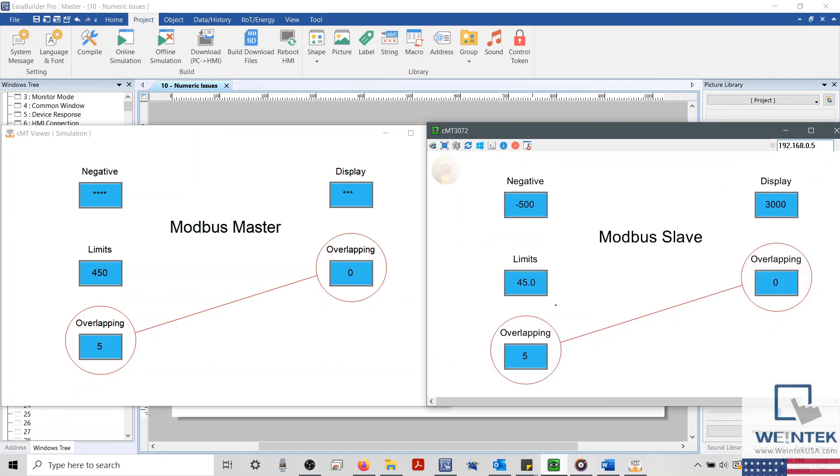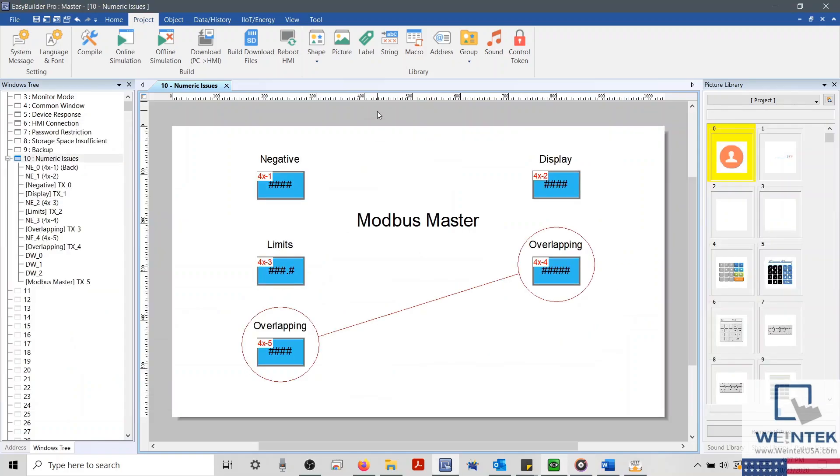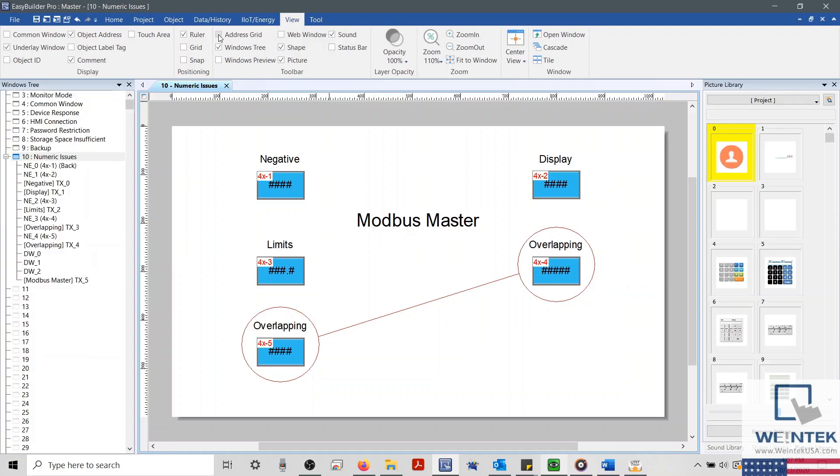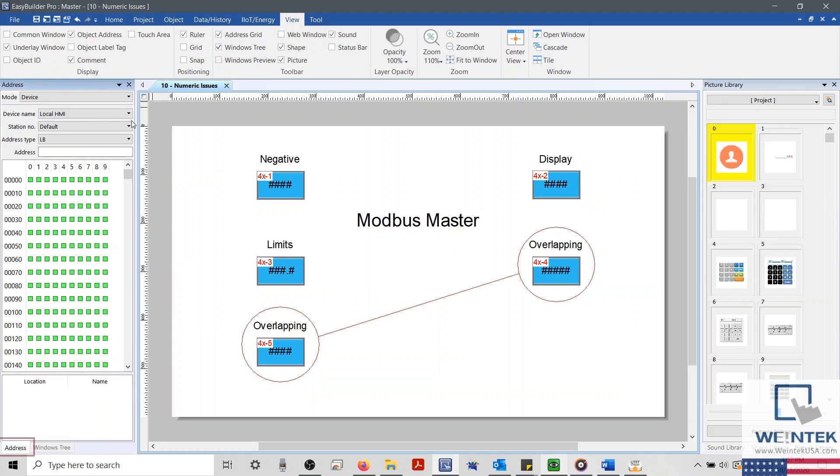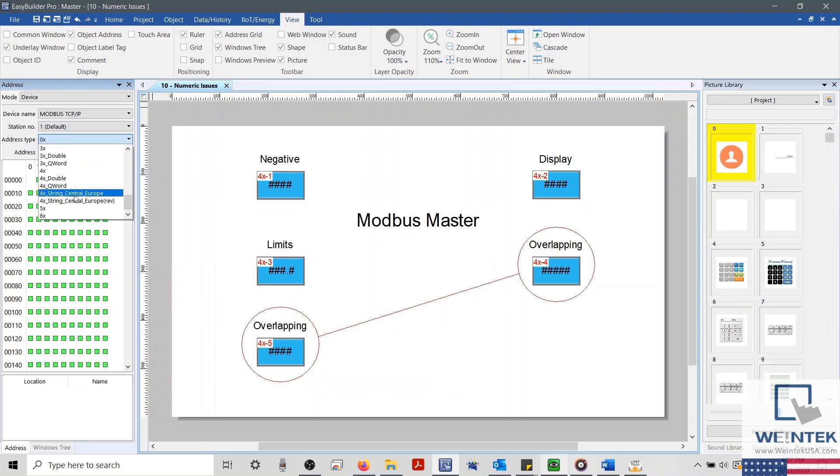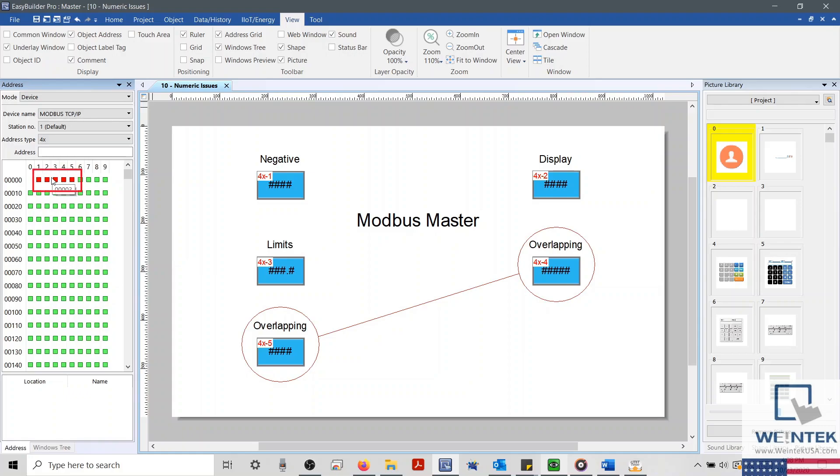To access the Address Grid, I'll select the View tab, and then enable our Address Grid. I'll then select the Address tab on the bottom left. It may be on the bottom right depending on your configuration. And we'll see a grid with several green boxes at the top. And I'll select my Modbus device. Since I only have one station number defined, I'll select the Address Type dropdown list, and select my 4X registers. And we'll see that we now have five blocks within our green grid. Each block represents a different Modbus or external device register that has been accessed by the HMI.